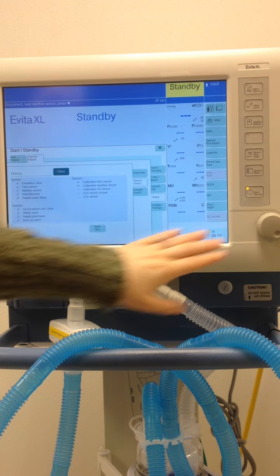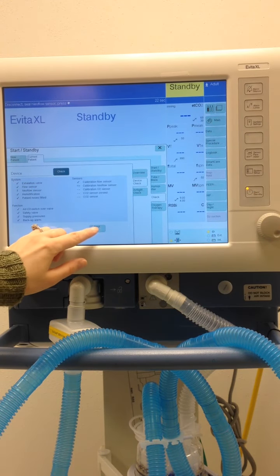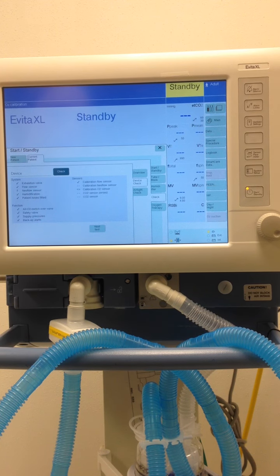Disconnect seal Neo flow sensor and press your knob. We're not doing that because we don't have a Neo flow. So next test. It's going to tell you that was aborted. That's fine. It's going to calibrate your O2. That calibration was okay. Park CO2 sensor. We're not going to have the CO2, so we can just next test on that one. Again, CO2 sensor fitted into the cuvette. Next test, because we're not doing CO2.